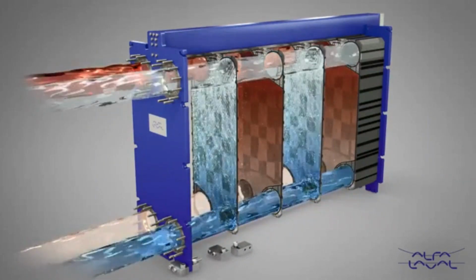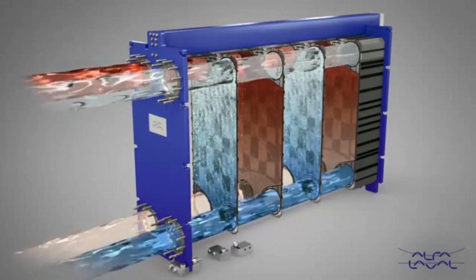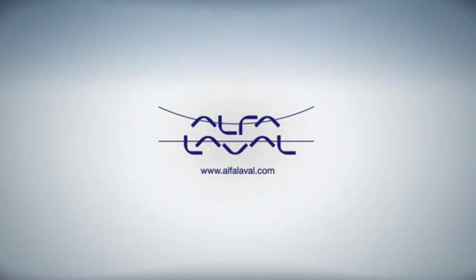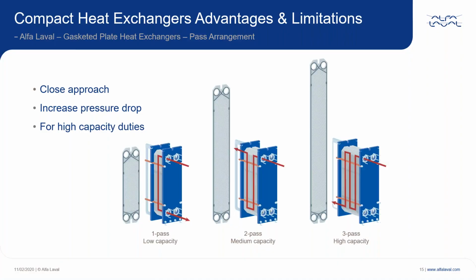So this shows a counter-current flow, but you can have a co-current flow with both fluids going in the same direction. Often that's preferred in some oil duties, crude oil, and also in some fine chemicals where the plate wall temperature is important to avoid any waxing or product degradation. Okay. With our gasketed plate heat exchangers, we have fixed plate sizes. So in the instance of very high duties, it's possible to make multi-pass designs, as there's no plate that fits every single duty. So having a multi-pass, you can increase the surface area and save space, in effect, by making the plate taller than what it actually is.